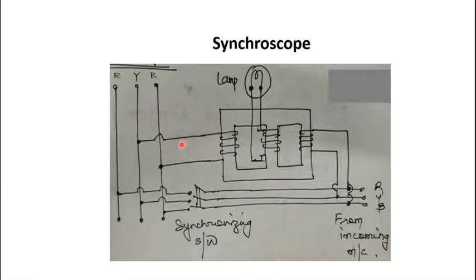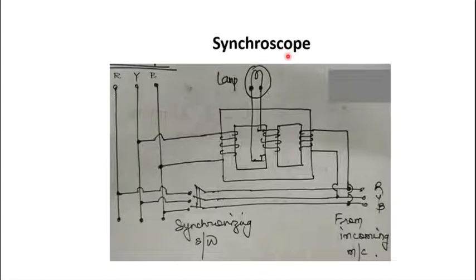The last instrument we will discuss is the synchroscope, in two types: conventional and electrodynamometer. Before going into the synchroscope, we need to understand why it is required. From the theory of transformers, whenever we want to connect two transformers in parallel, conditions must be matched — such as the X-to-R ratio and zero phase difference — otherwise circulating current will flow. The same applies when connecting two alternating sources in parallel, as we don't want current flowing between the sources, only through the load.